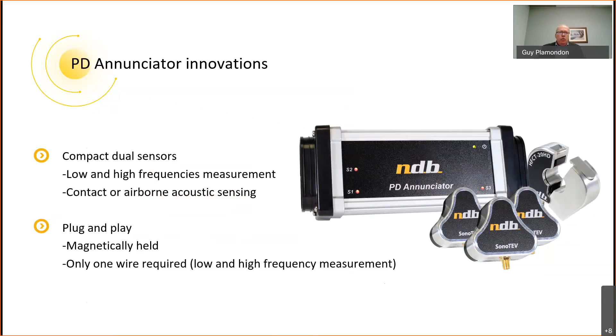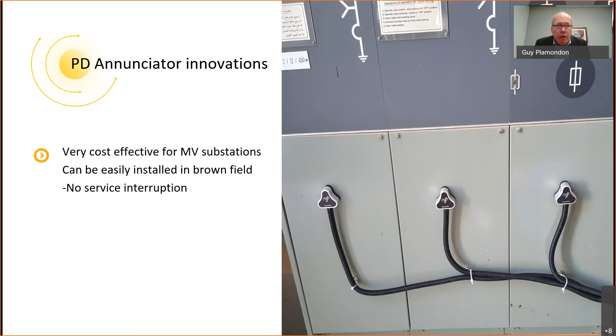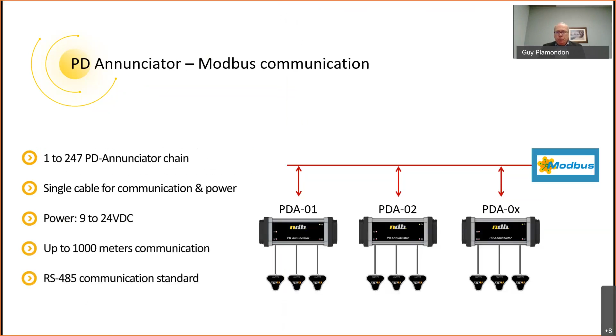An example of a sensor installation in a new switchgear is, in this case, we use an acoustic airborne sensor. So it's installed inside of the cable box. We have sensors that can be installed outside, so those are very cost effective for medium voltage installations already in the field. I mean the brownfield, where there's no service interruption. We use Modbus communication, so we can easily chain multiple alarm systems together and then send information to a SCADA system using the Modbus protocol.